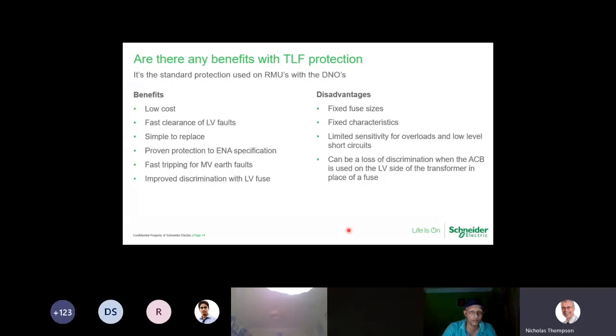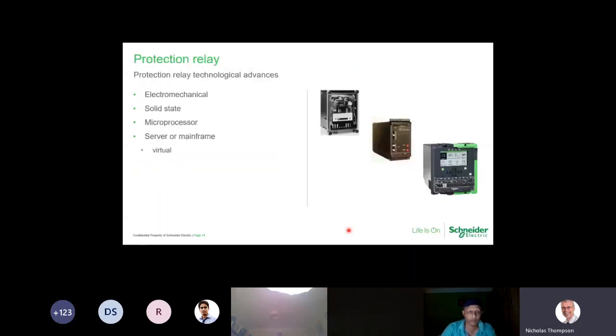So these are the benefits, these are the disadvantages. At the end of the day, the choice is down to the end user as to what they want. If they want something simple, relatively cost effective, then time limit fuse is the way forward. If you need something a little bit more sophisticated, then you're going to need to move to a protection relay. Now, moving on to protection relays, and this is now into the scenario of primary distribution switchgear. They've moved through various technological changes. Changes in technology in protection relays tend to be a little bit slower than what we would experience with our TVs and mobile phones.